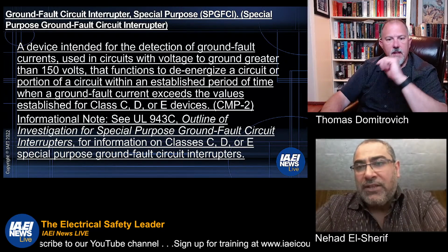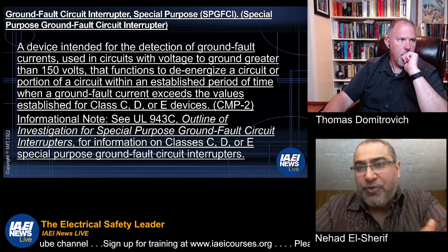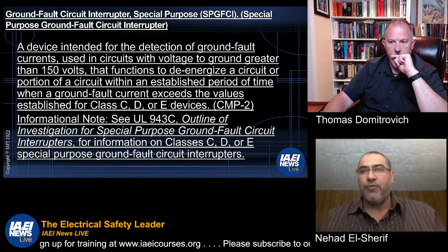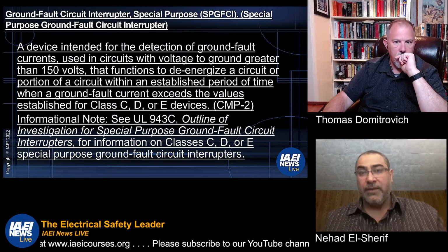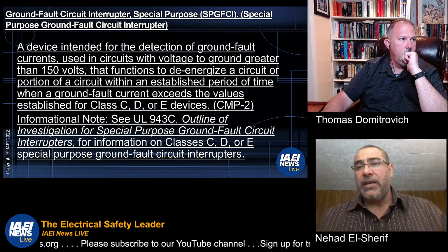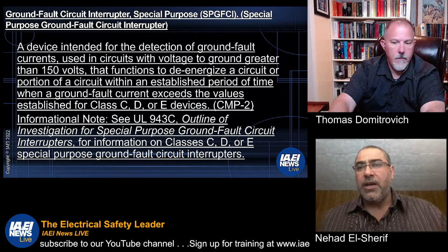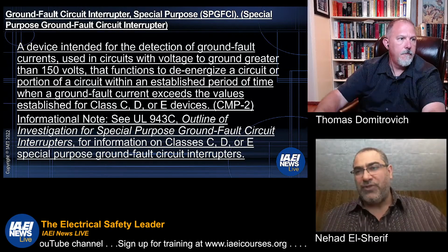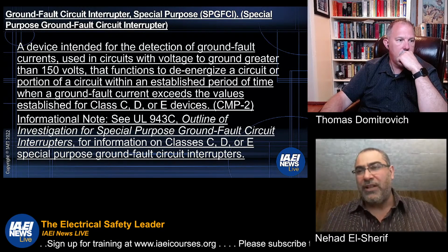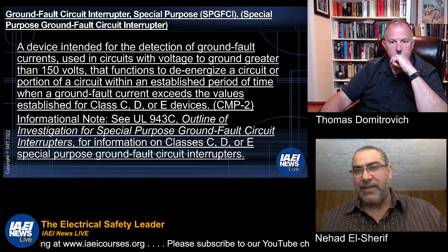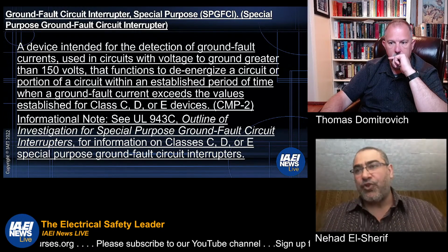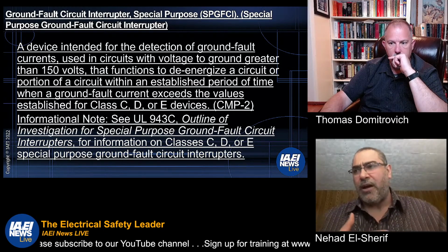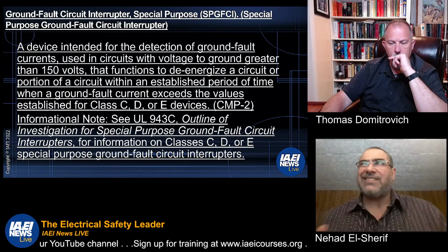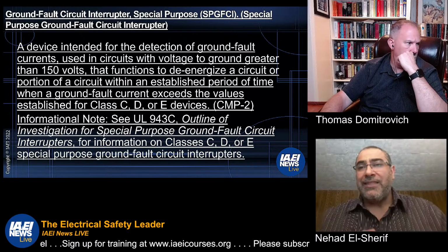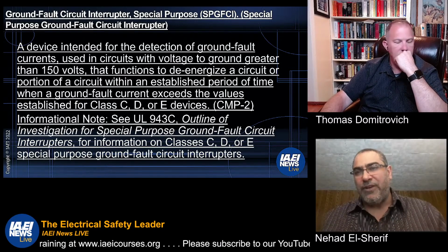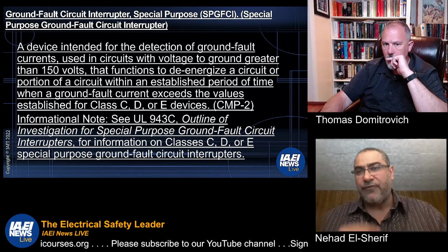So 150 volts to ground is key, and it's the differentiation between special purpose and Class A. I guess we have to use classes now because we can't just say GFCIs anymore: Class A GFCI, and special purpose for Class C, D, and E. Yep. The other thing I'd like to point out in the definition, Tom, is that the standard governing these new classes of GFCIs is called UL 943C. The C is not to be confused with Class C. UL 943 is the Class A GFCI standard. Then there's UL 943B, the appliance leakage circuit interrupters, another class of equipment used for protecting appliances like hair dryers. And the third member of the 943 family, 943C, is the outline of investigation for special purpose GFCIs.